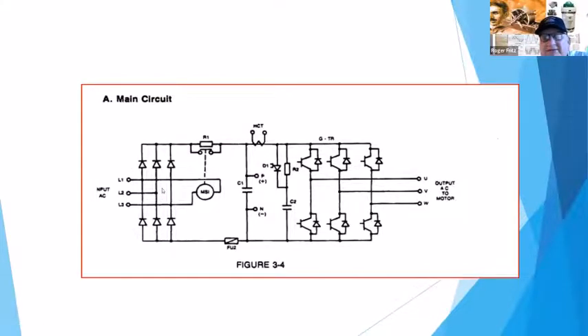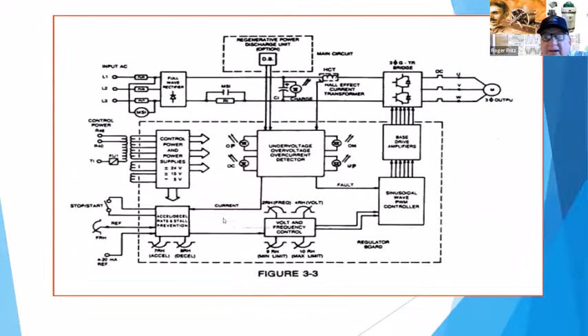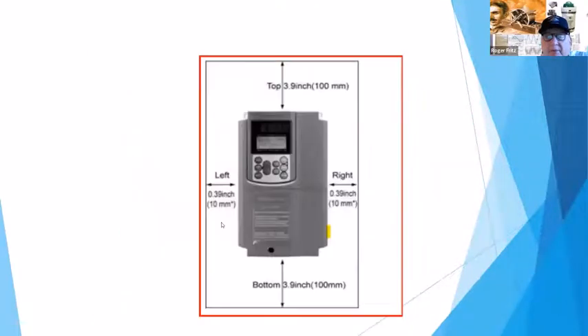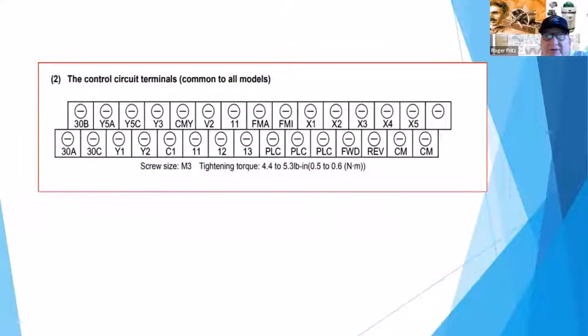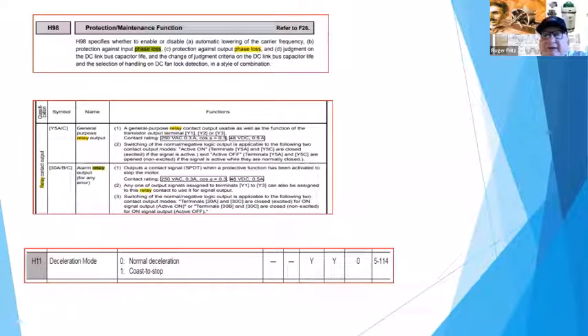So the main focus, you've got to have these diodes heavy enough. Normally on a single phase application, they'll use a 3-phase drive, but they'll just put 2 phases into it. But it just has to be double the size on the input to handle those currents. But the motor will still function as is. Plus you get soft starting. So it has eliminated a lot of the need for phase converters that are out there, like the rotary phase converters, which had a capacitor where they gave it one shot of a capacitor at a different phase angle to get it up and turning. They're still running on single phase, but you had to oversize the motor dramatically. Fairly inefficient when you did it the old way. So this is an advantage if you want to use them on single phase power.